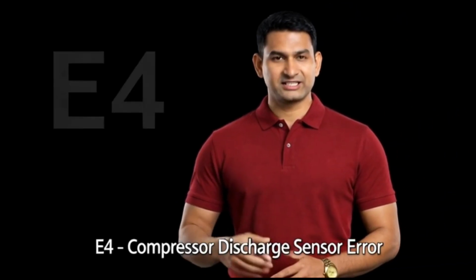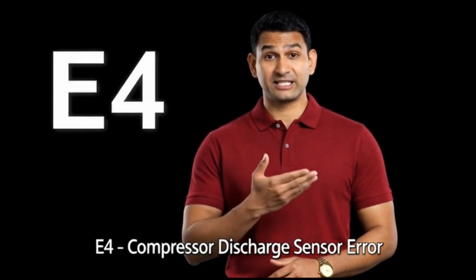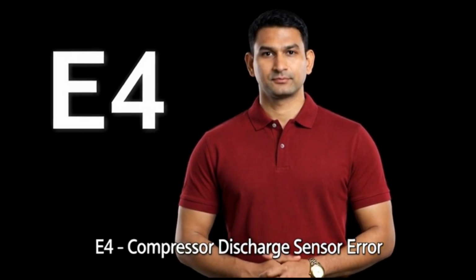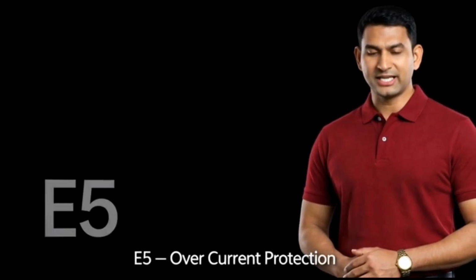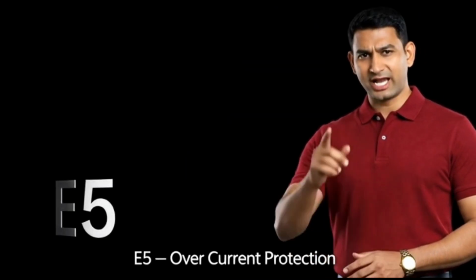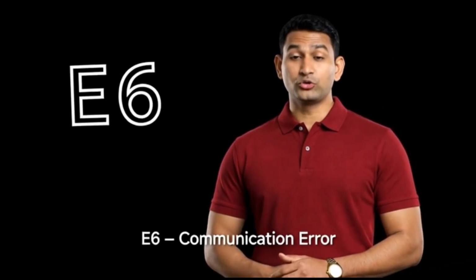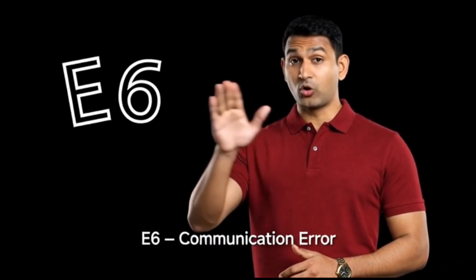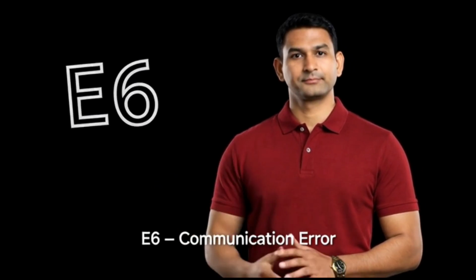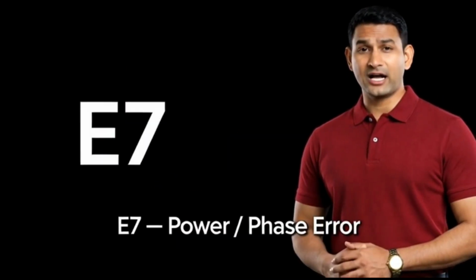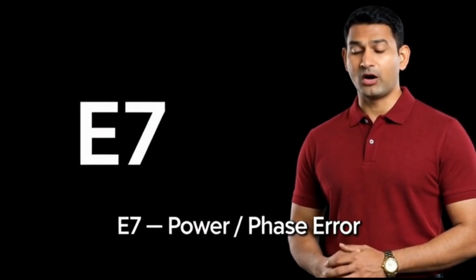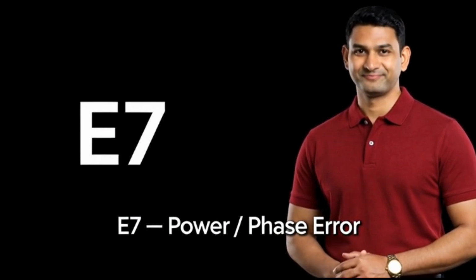E4 error signals the discharge temperature sensor of the compressor is faulty. E5 error occurs when the AC is drawing too much current. Check power supply and wiring. E6 error shows a communication failure between indoor and outdoor units. E7 error happens due to unstable power supply or incorrect phase connection.